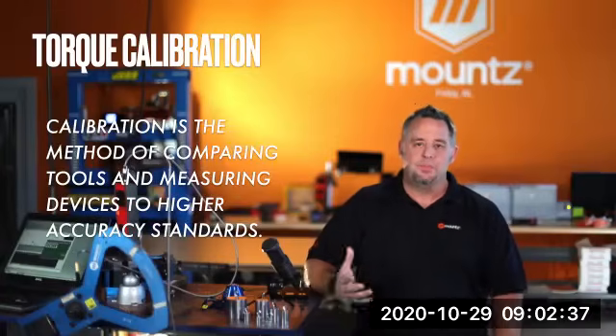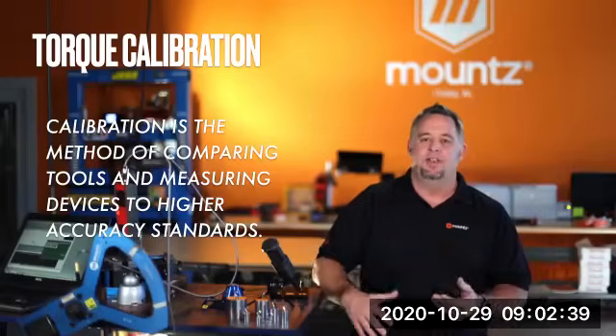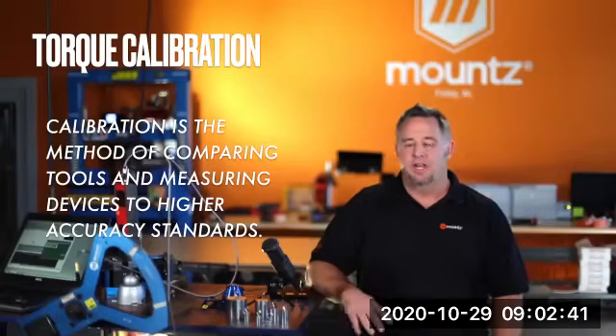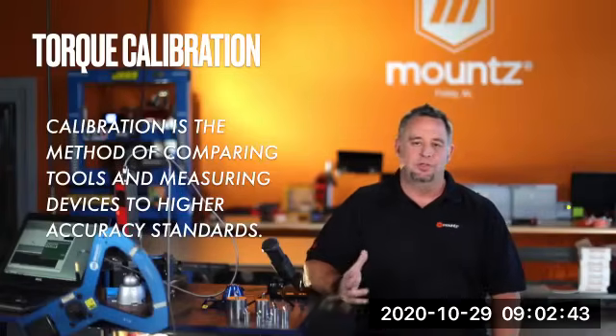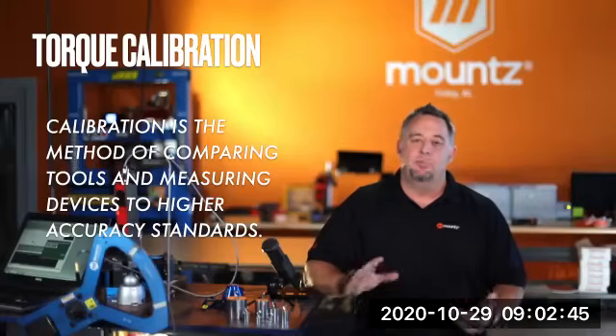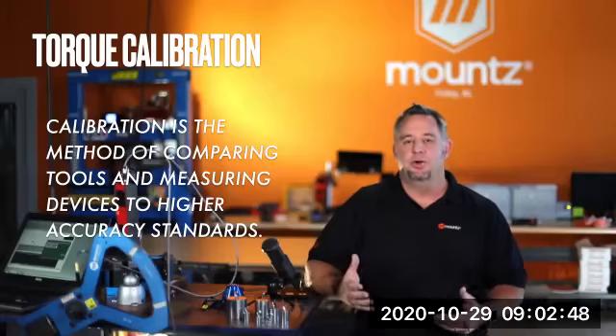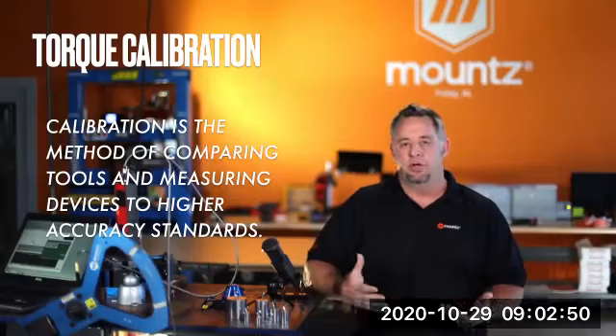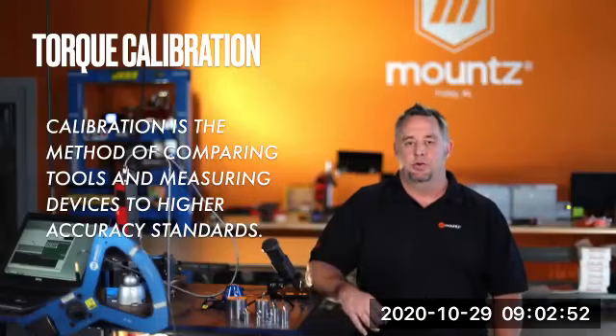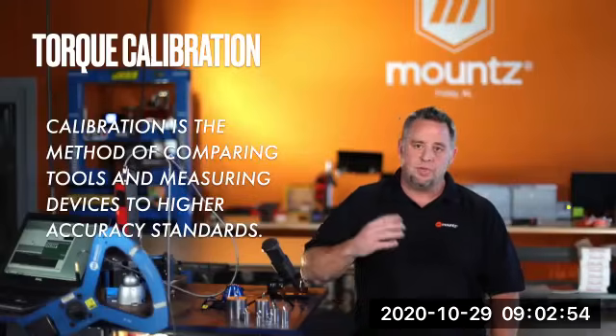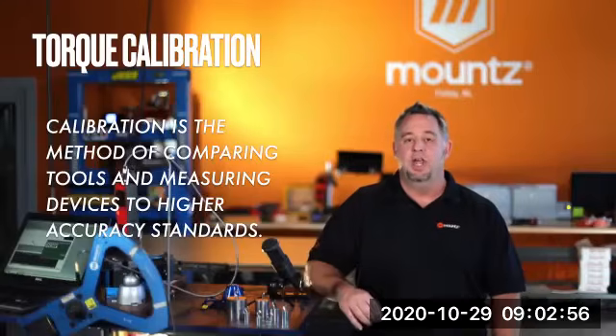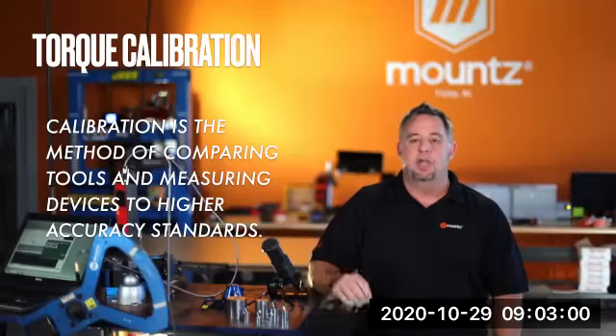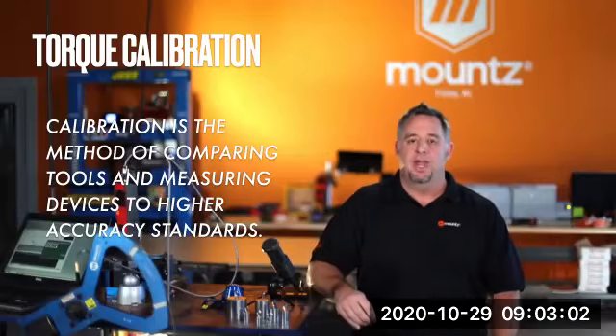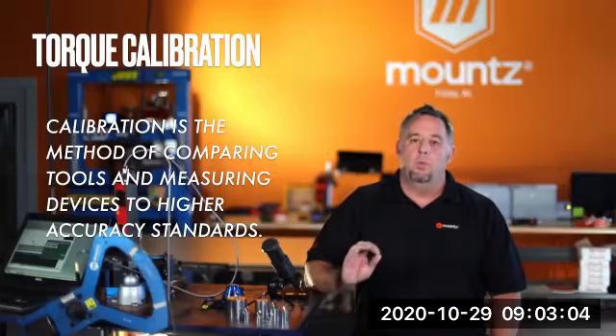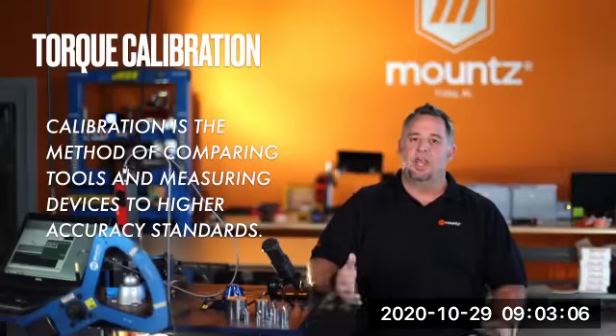So when we look at the whole calibration process, what we're going to do today is we'll take a look at the process itself, the equipment that you're going to need to do it if you wanted to bring that in-house, and we're also going to do a run-through of a three-point calibration here for you this afternoon. So with the torque analyzers and the sensors.